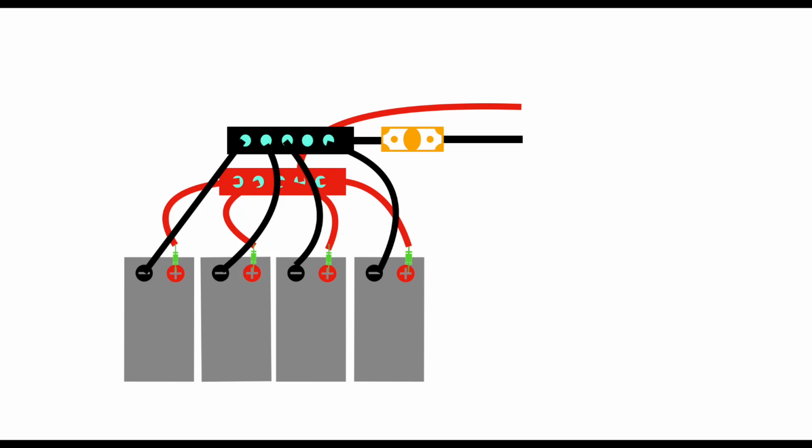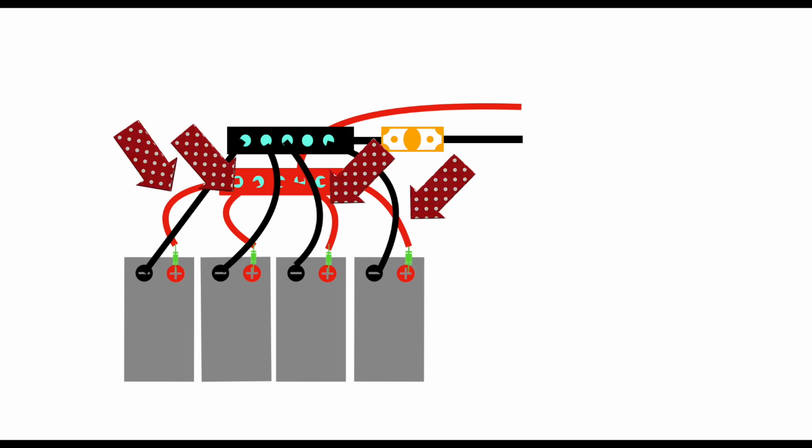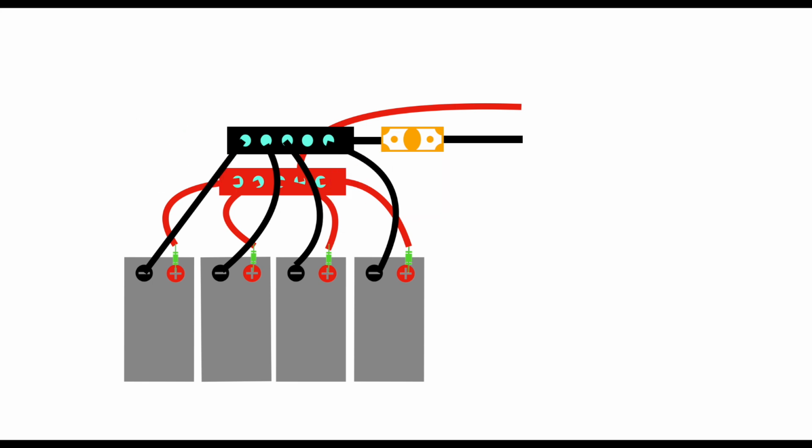Wherever you put the fuse, remember that it must be sized in accordance with the cable it's there to protect. For example, this cable here is much bigger than the four preceding it at the bus bar. Therefore, the fuse protecting it must also be bigger.